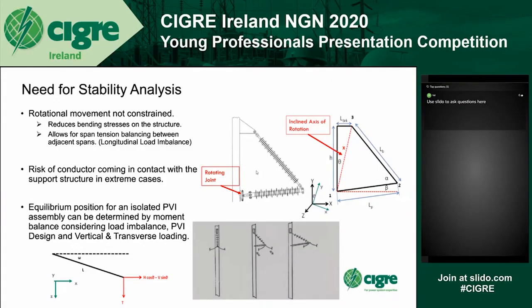This rotation reduces the bending stresses on the suspension structure, but also allows for span balance, balancing tension between adjacent spans in case of longitudinal imbalance between them, as the PVI assembly swings towards the span with higher tension. However, in case of large imbalance between span tensions, high enough rotation in a PVI assembly can be induced, which can lead to clearance infringements and even contact between the conductor and the support structure in extreme cases.